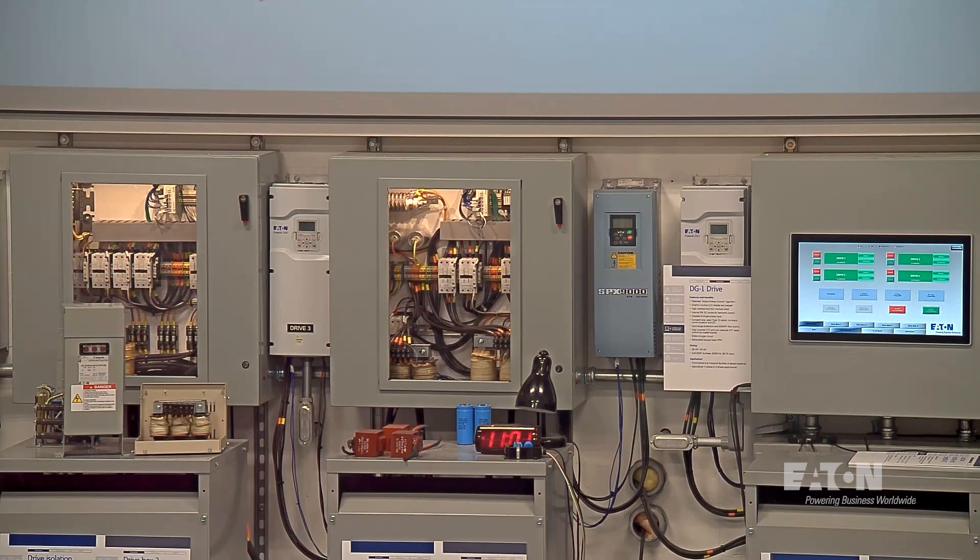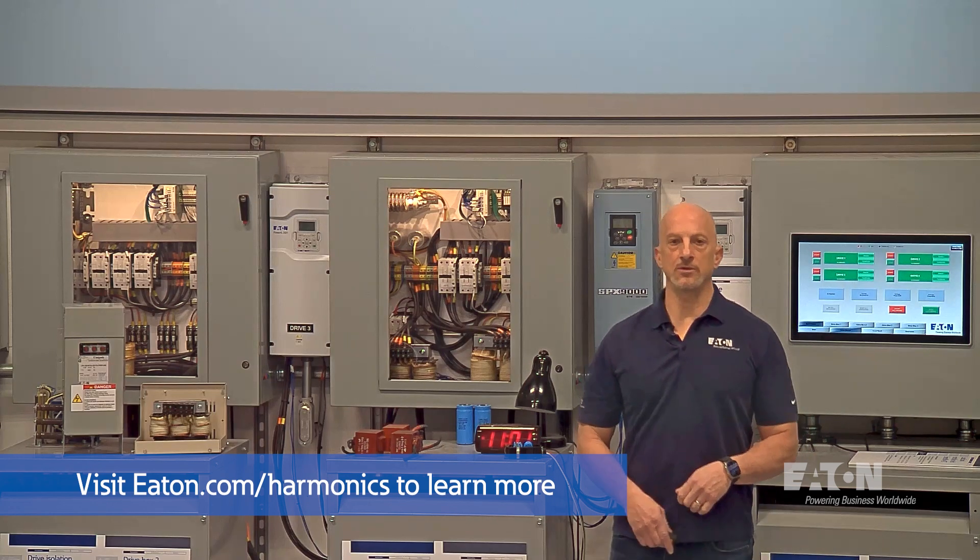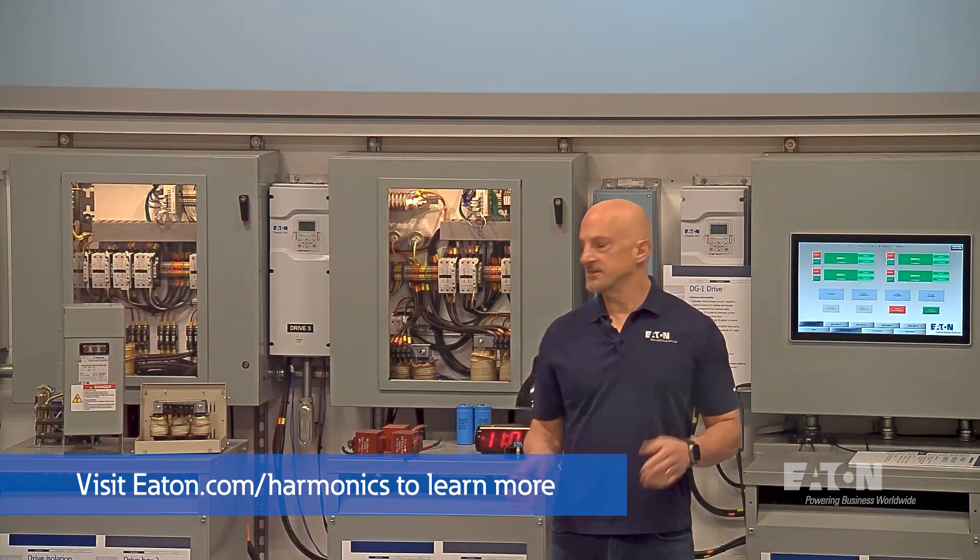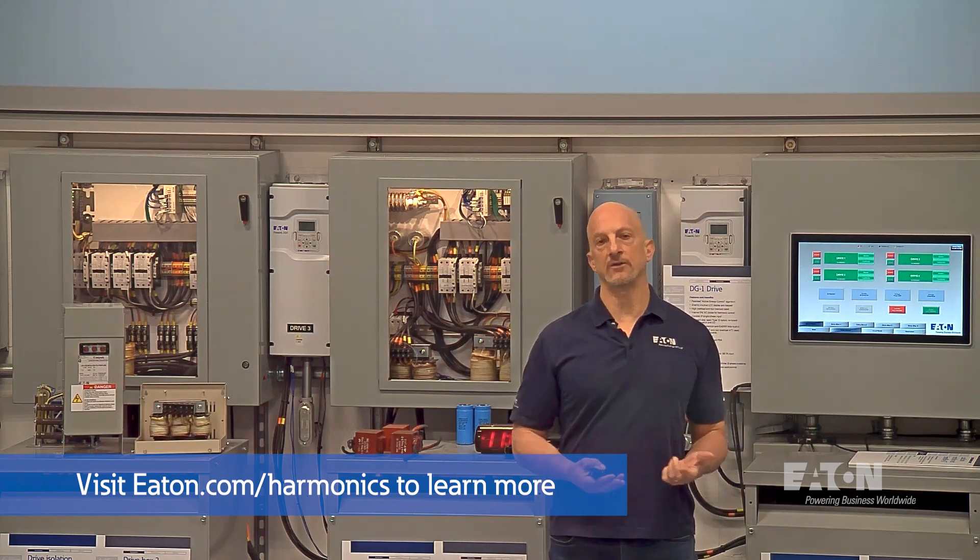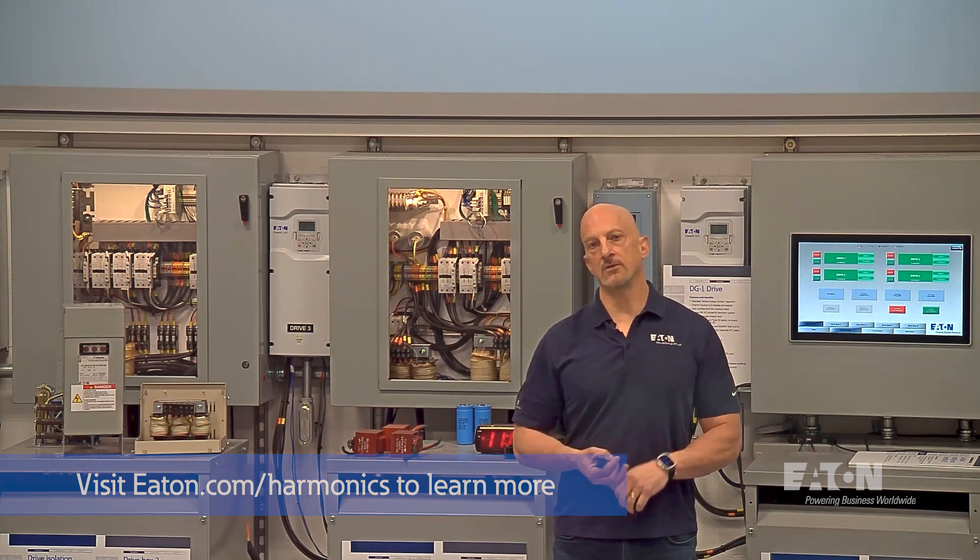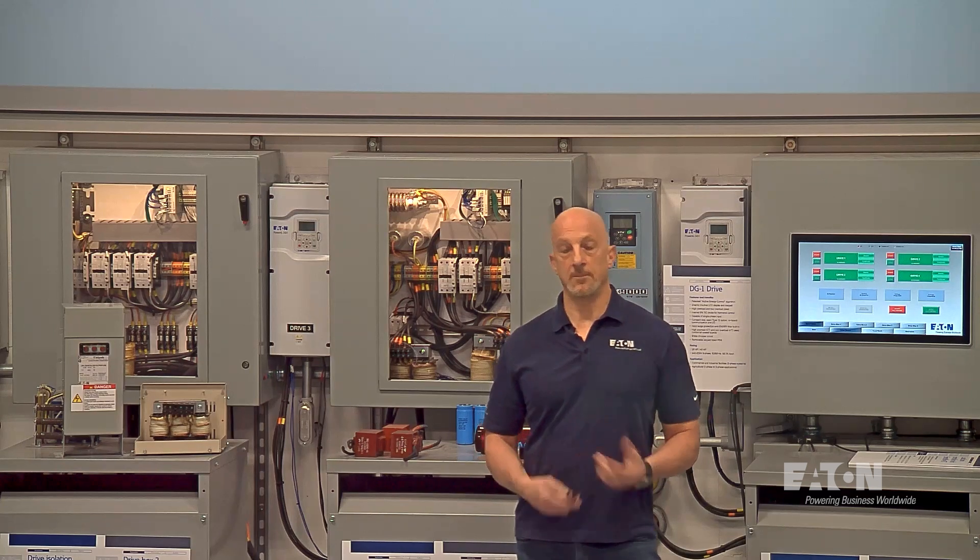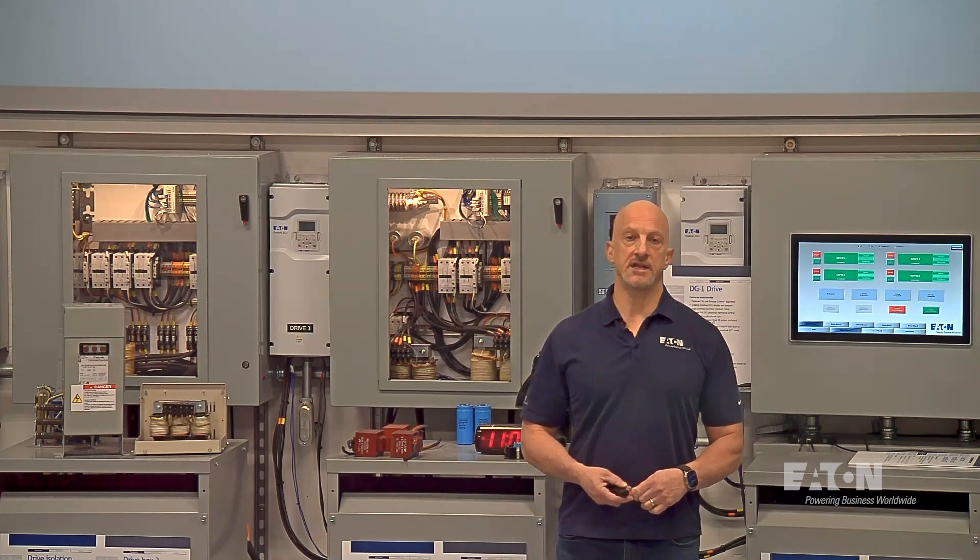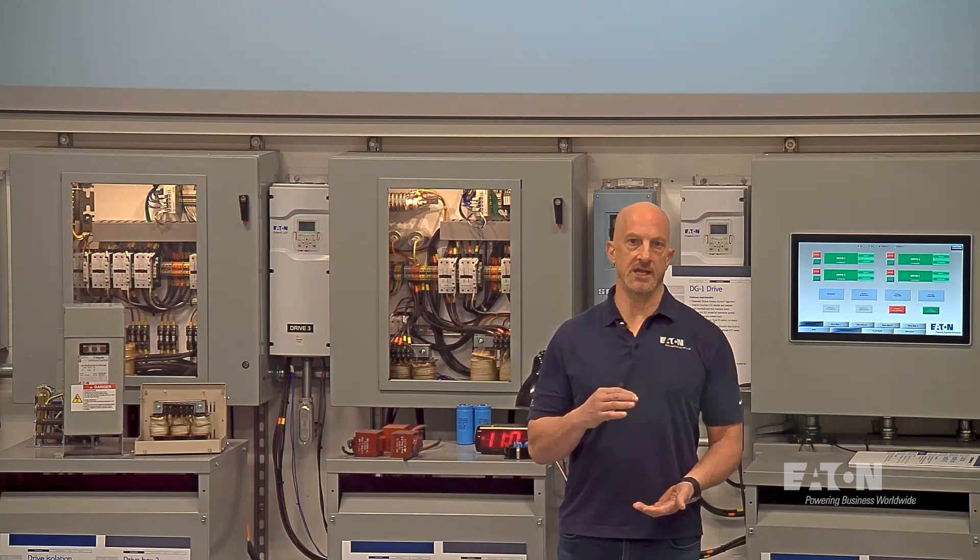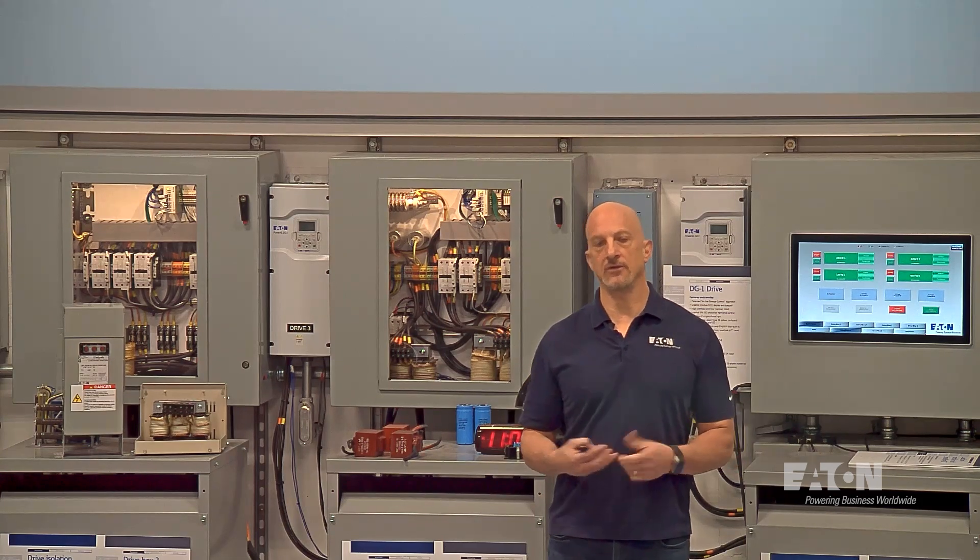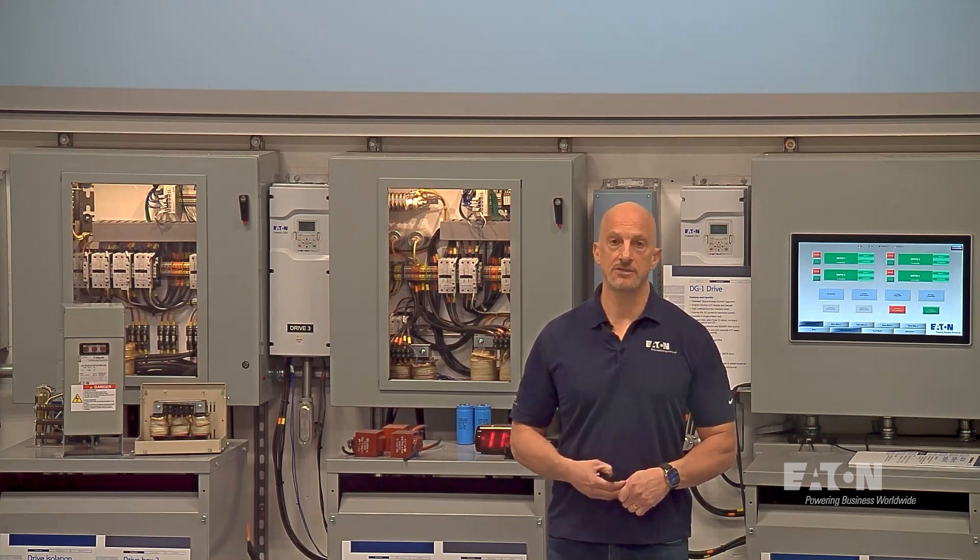And this is all stuff that really comes into play when you're designing filters. Select the capacitor based on power factor requirements, select the reactor to tune to a certain frequency, and make sure both have the capacity and the withstand to handle the overvoltage in the case on a cap and the current ratings on both, and especially on the reactor side.